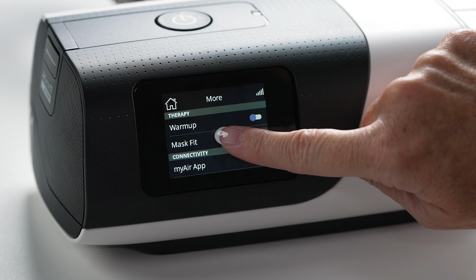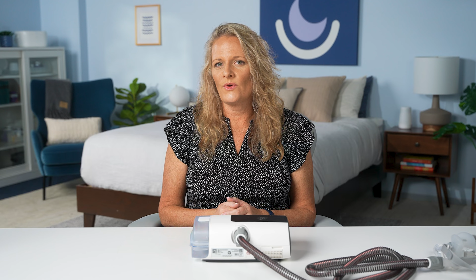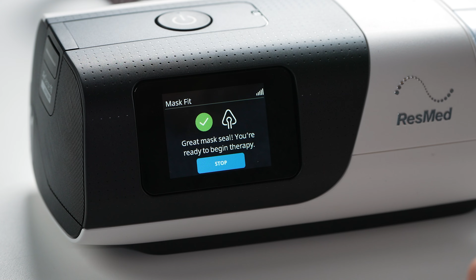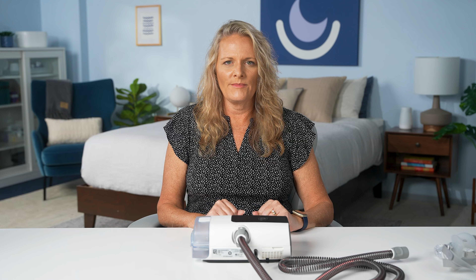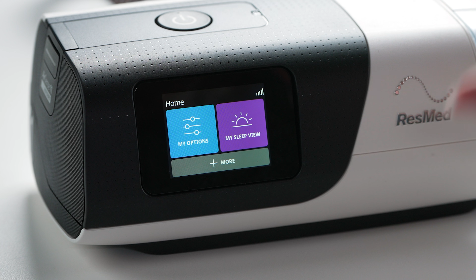The next thing we can do is run a mask fit check. In the AirSense 11, it's going to be in this plus menu. You can run a mask fit check by clicking here. Put your mask on and click Start. The machine will then run a pressure check to make sure that the mask has a proper seal. If you're getting this exclamation point, then adjust the mask tightness until you receive a check mark. Once that check mark is there, you know that the mask has a proper seal and you're ready to go for the night. Lastly, the machine does have the ability to do a warm-up or preheat feature for your humidifier. That is also in this menu. That allows about 20 minutes for the water chamber to get to a proper temperature. Hit your house and that takes you back, and that's the menus of the device.